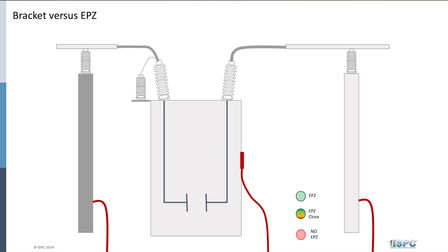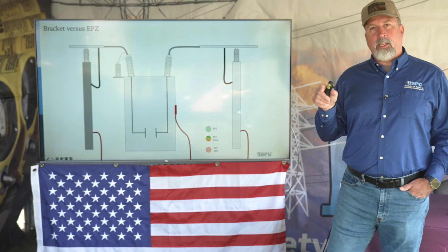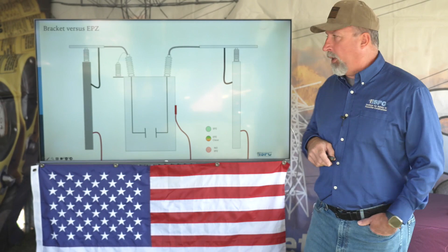Same thing in a substation. If we install bracket grounds here right now, looking at this picture with those two bracket grounds installed, the only potential place for a difference of potential is at the open contacts internal to the high voltage cabinet of the breaker. You can see the contact right here. Breaker's open. That's your only point of difference of potential, and you're not going to get across that because it's internal to the breaker.